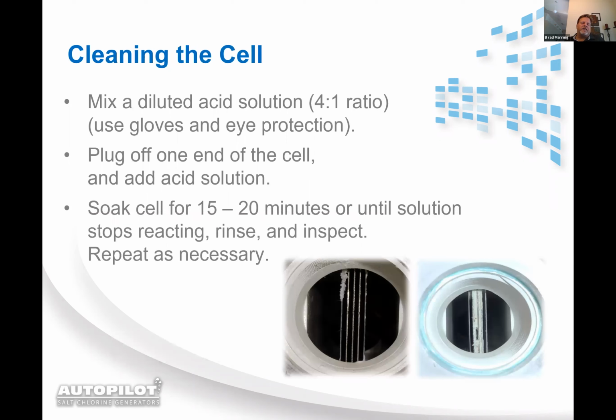After you've cleaned the cell and removed all the calcification on it, you want to look down through the blades, make sure that you don't have any calcification in the middle of those blades somewhere. You want to get them all good and clean. Typically, the way it works is you can use a 1.5-inch drain-out clean-out plug to plug the bottom of the cell.